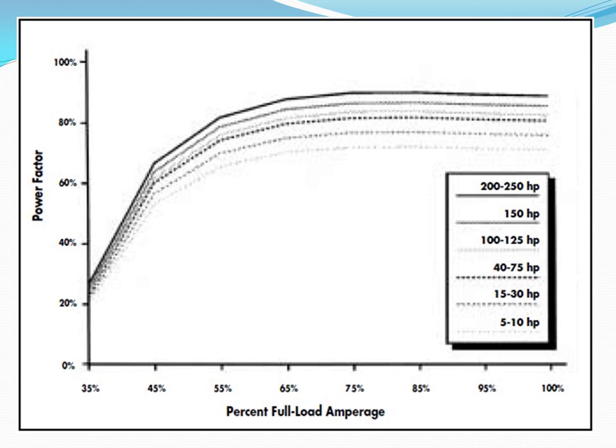Looking at the relationship between percent full load amperage and power factor, we notice that motors operating above 65% full load do not have a significant change in the power factor. This helps to determine that for many motors, we only require a fixed size corrector.